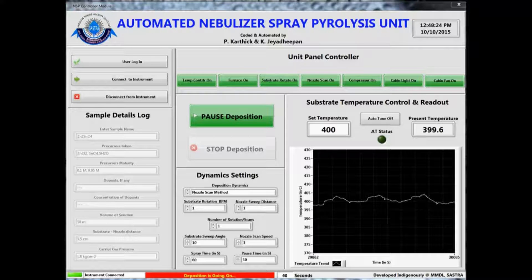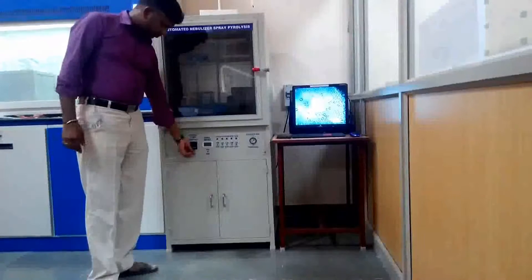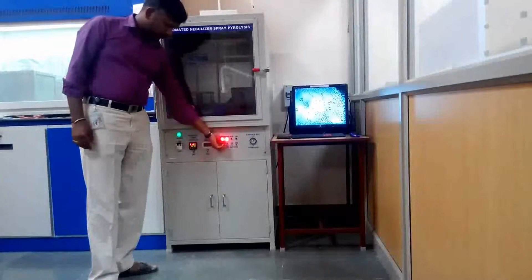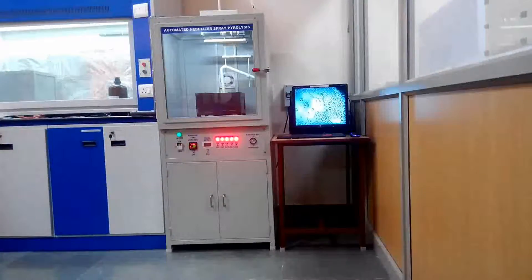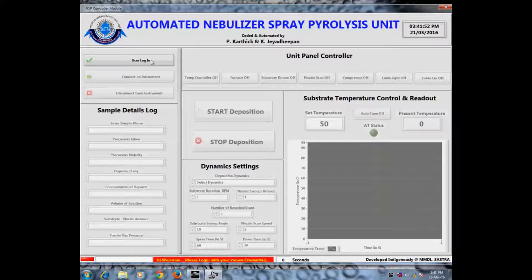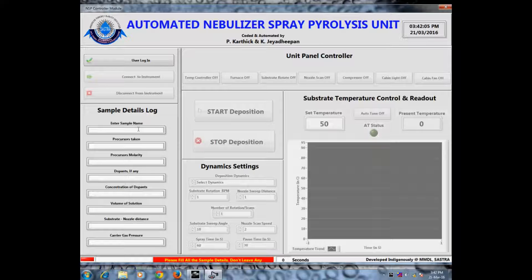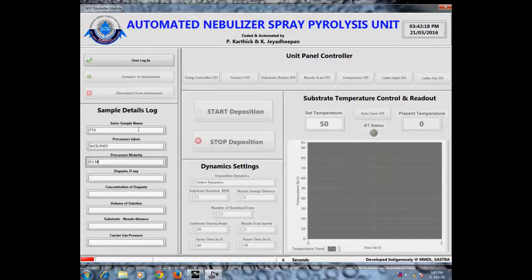This is all about the instrument. Now a short demonstration is going to be given to successfully prepare a film using the instrument. At first, the instrument should be powered up and all the manual override controls on the control panel should be switched on. An AND operation is implemented between the front panel controls and the software controls; hence, even though the front panel switches are on, they should also be switched on in the software. The software should be accessed with correct login credentials created for a particular operator. The software already has an admin login through which only calibration and tuning of the instrument can be done. The sample details must be entered for logging purposes and for recognizing the samples in future. Only after a successful log entry can the instrument CPU be connected from the software.